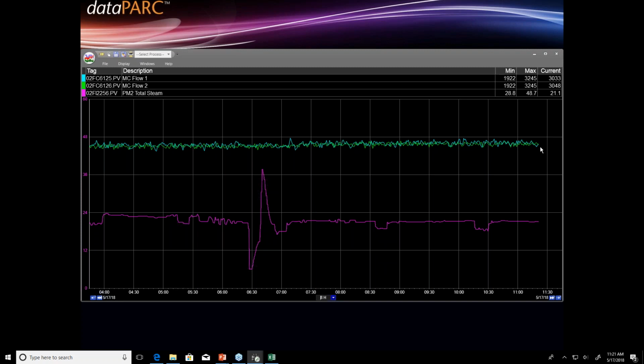Well, the way the trend works is we leave a certain period of time on the right-hand edge for current values as they come in. And that's being set by something called the normal future percent property in trend configuration. And so what will happen is if you just sat here and watched this in real time, the trend lines would build out to the very right-hand edge of the display, and then it would shift again by that normal future percentage.